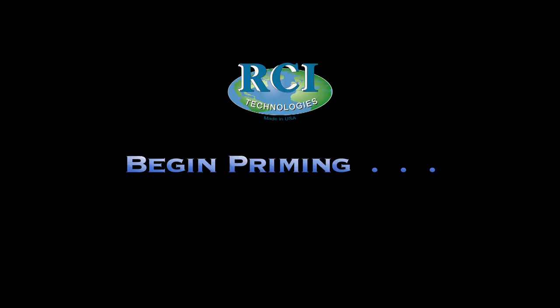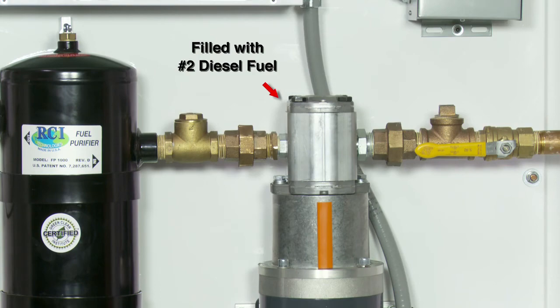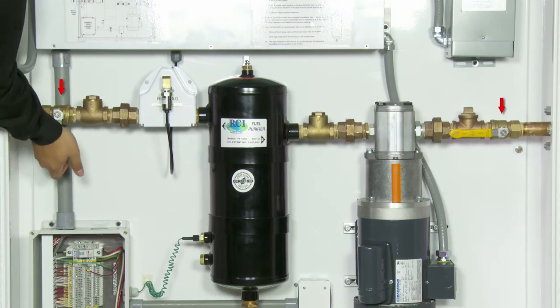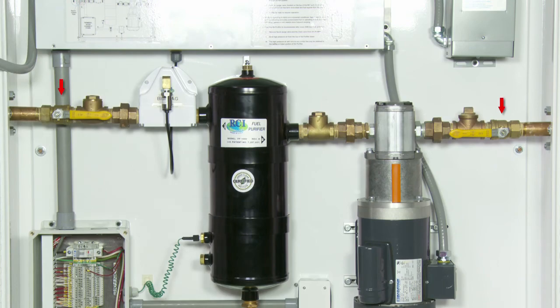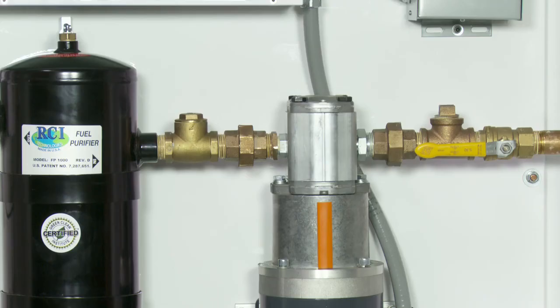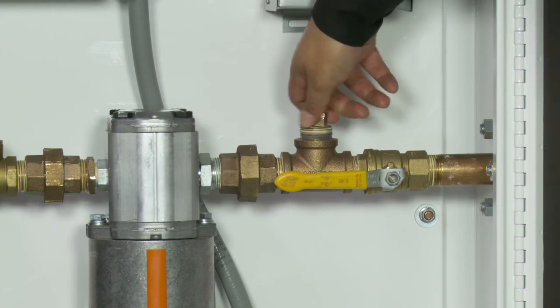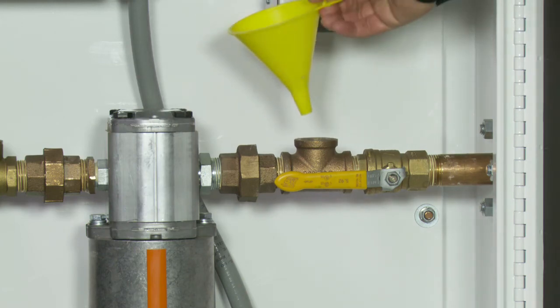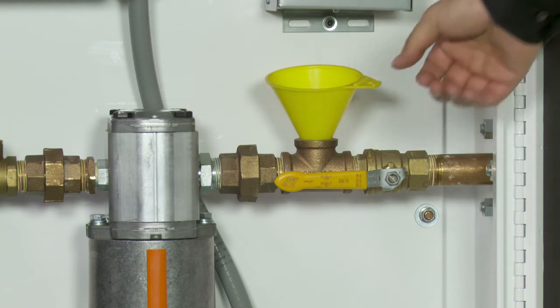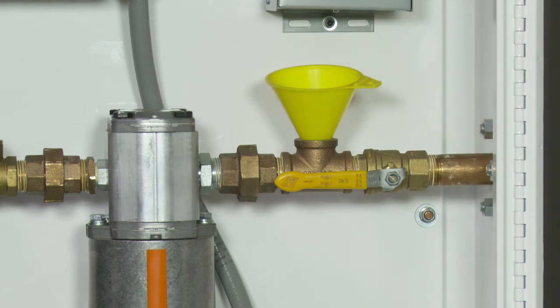To begin priming, first make sure the pump is filled with number 2 diesel fuel. Next, ensure that all ball valves are in the open position. If the pump inlet port of the FRS 660 is located below the fuel level in the tank, close the inlet ball valve. Now, open the priming tee, fill the line with fuel, then close the tee. Note that for tanks situated on a lower level than the FRS 660, it is recommended that a foot valve be installed at the fuel tank to maintain prime in your system.